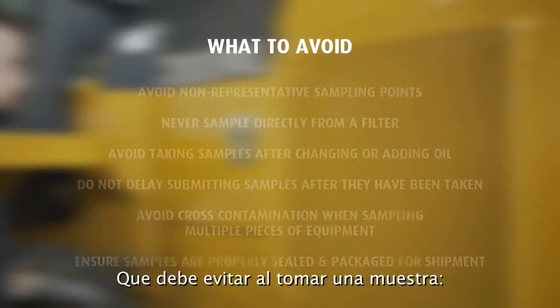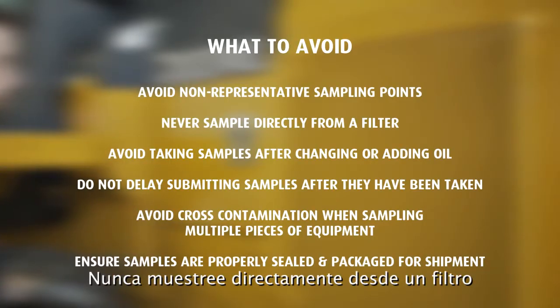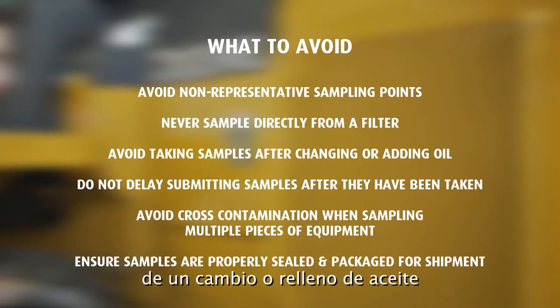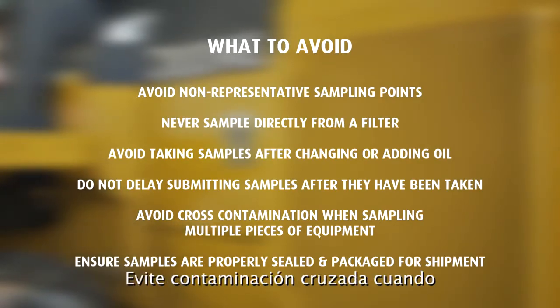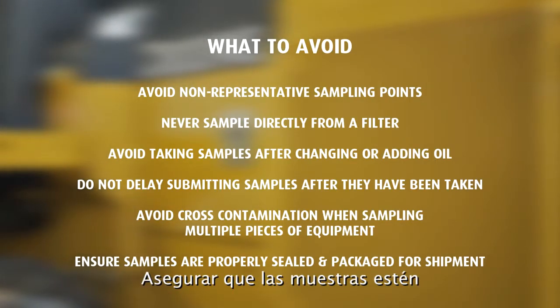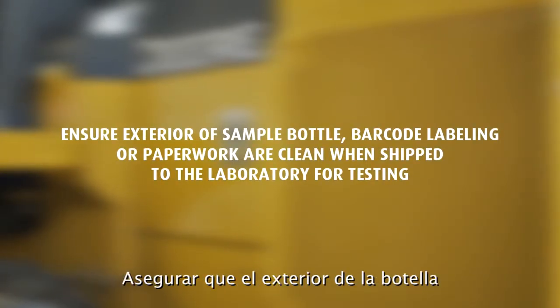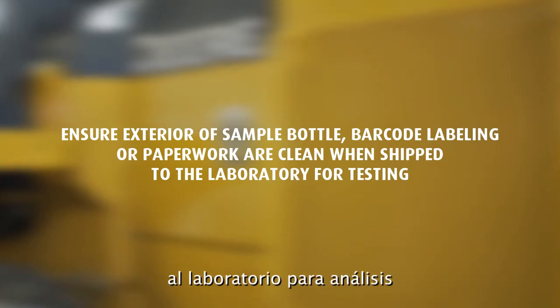Things to avoid when taking a sample: avoid non-representative sampling points; never sample directly from a filter; avoid taking samples after changing or adding fresh oil; do not delay submitting samples after they have been taken; avoid cross-contamination when sampling multiple pieces of equipment; ensure samples are properly sealed and packaged for shipment; and ensure the exterior of the sample bottle, barcode labeling, or paperwork are clean when shipped to the laboratory for testing.